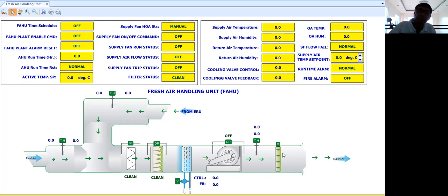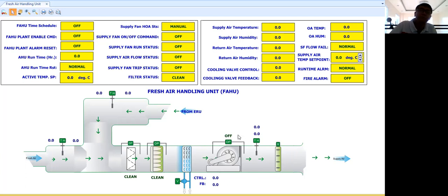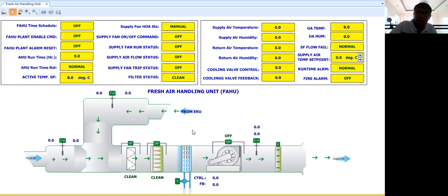There may also be a supply damper. The purpose of this supply damper is that if there is a fire, the control logic program will stop the fan and you can also close the supply damper if it needs to be controlled by the BMS. Before you write your control logic program, you need to look for the approved sequence of operation for this fresh air handling unit.